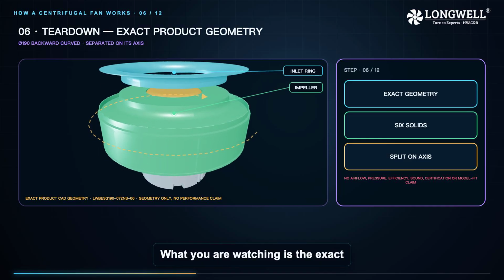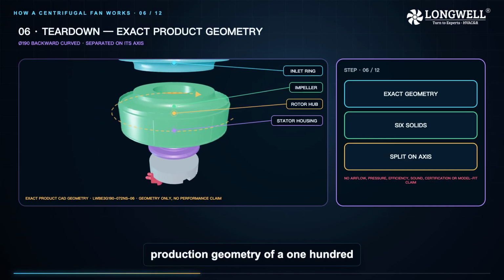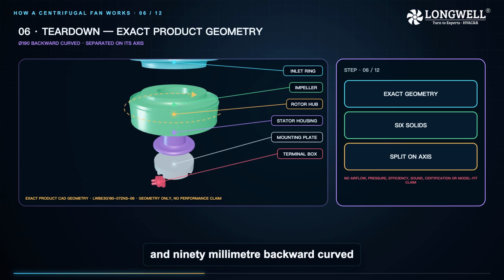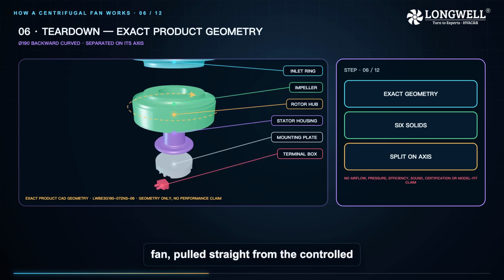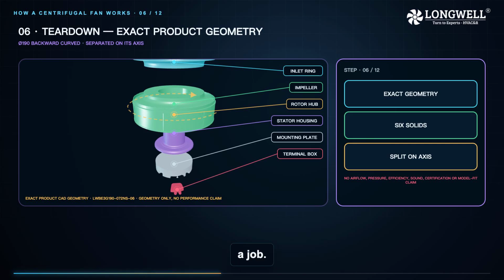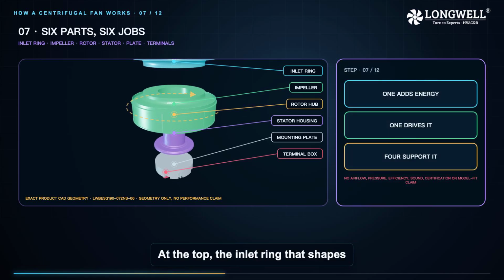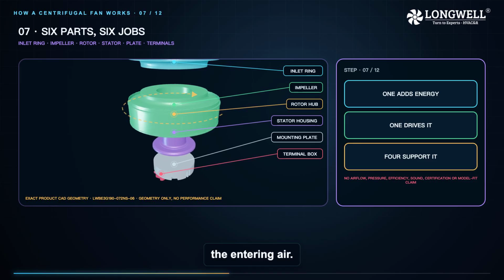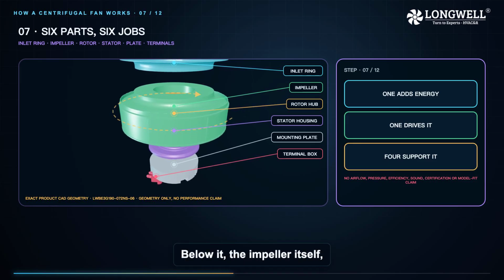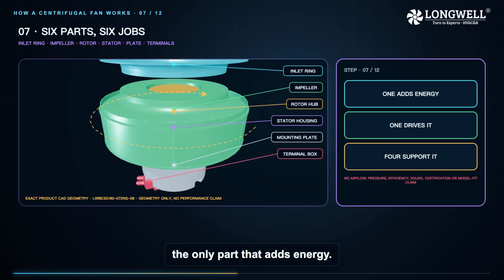What you are watching is the exact production geometry of a 190mm backward curved fan, pulled straight from the controlled engineering model and separated along its own axis. 6 parts, and every one of them has a job. At the top, the inlet ring that shapes the entering air. Below it, the impeller itself, the only part that adds energy.